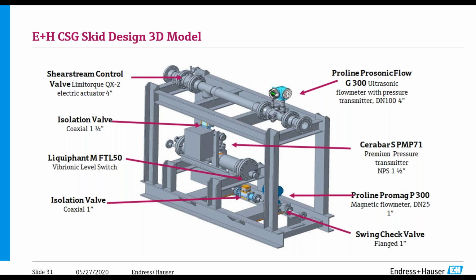In coal seam gas, in a lot of wells where there's a higher flow profile of the gas, there's a lot of solids carryover, and the solids carryover is primarily coal fines and sand in some cases, and of course that's very abrasive. I've already mentioned that this normally happens when we get higher flow rates. When the flow rate picks up, obviously the higher the velocity, the more abrasive it gets. So you've got an abrasive material coming through the flow meter, and you've also got a higher flow velocity, which is a recipe for the perfect abrasive storm inside a flow meter.